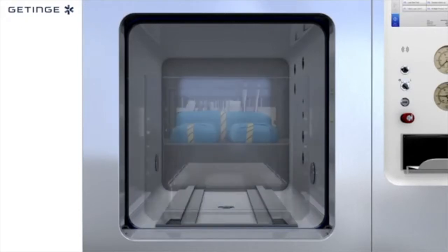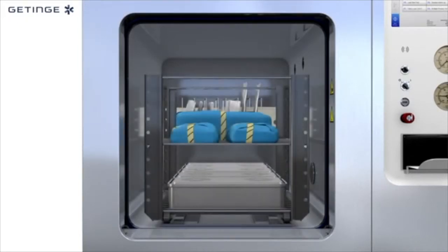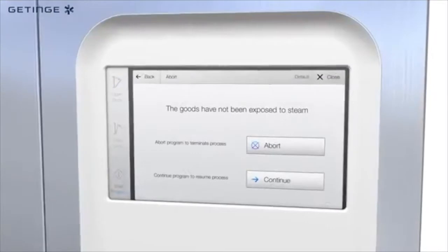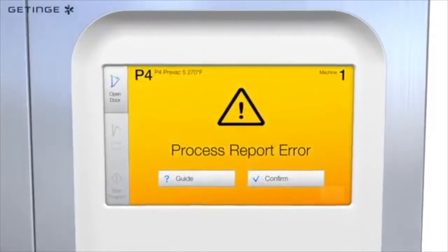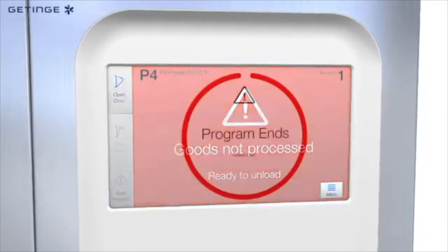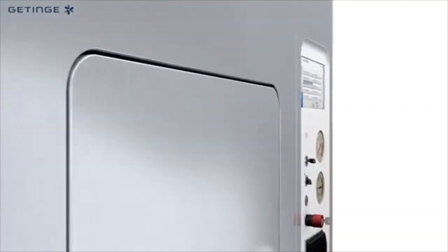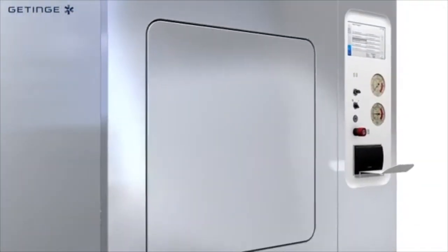However, humidity that's greater than 3% generates saturated wet steam, which requires higher sterilization pressure and temperature. Also, wet steam extends the drying time at the end of the sterilization process. Dry loads are required at the end of the process before equipment is wrapped.